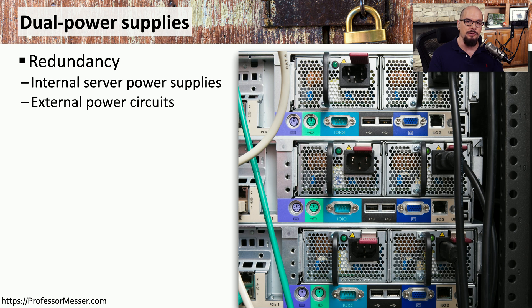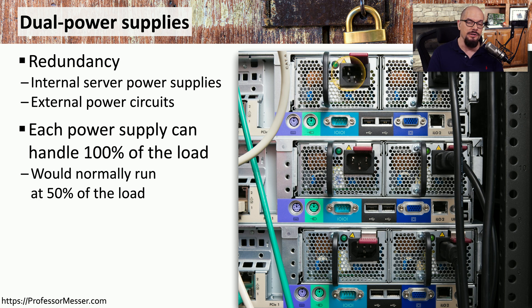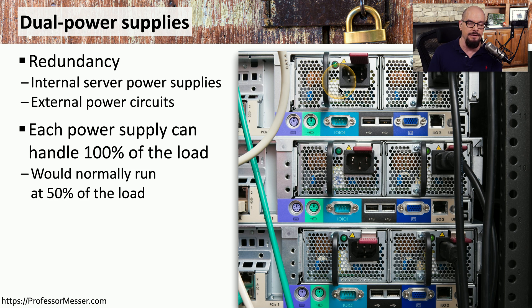If there's some type of hardware failure and the power supply itself fails, you might want to have a server that has multiple power supplies inside, where you can plug in multiple power sources. If you lose one of those power supplies, the other continues to provide power to the device. These power supplies are designed so that each individual one can support the power for the entire system. If you plug in one power supply, that single supply can provide 100% of the power load for that server. If you plug in two separate power sources, then each power supply will be providing 50% of the load. This picture shows an installation where half of the power is being provided by one particular power distribution unit, and there will be a separate power distribution unit that handles the power for the other side.